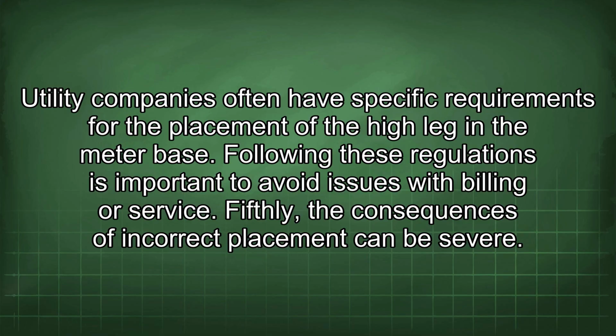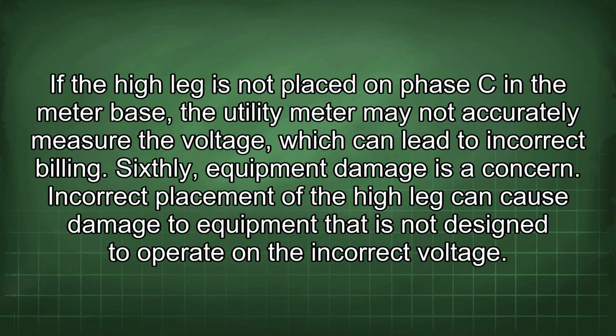Fifthly, the consequences of incorrect placement can be severe. If the high leg is not placed on phase C in the meter base, the utility meter may not accurately measure the voltage, which can lead to incorrect billing.